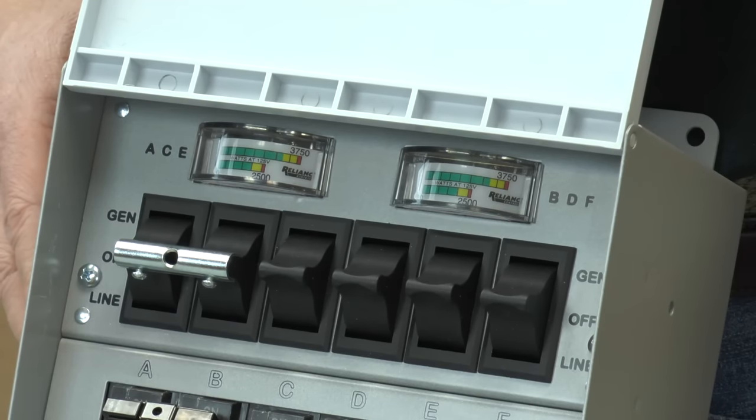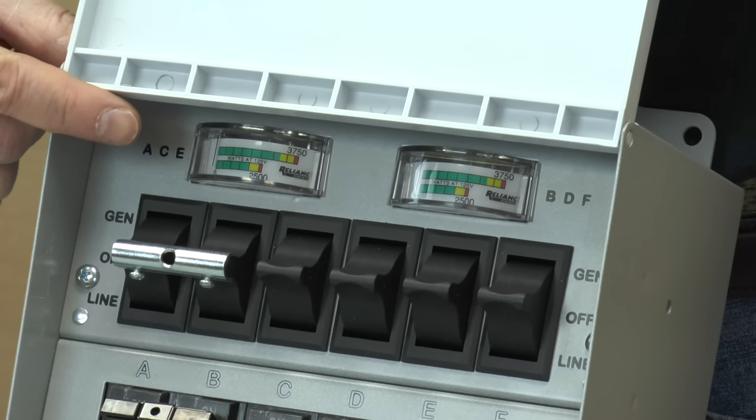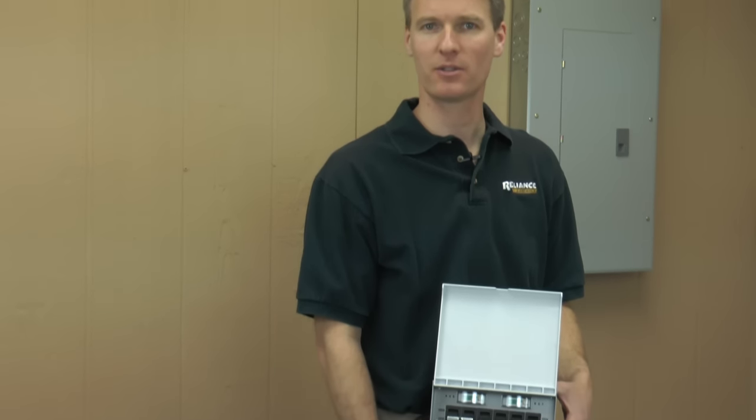When the generator is in use, these meters will show how much power is being used on each side of the transfer switch. Your generator will operate most efficiently if you can divide the power used evenly between the two sides of the transfer switch.